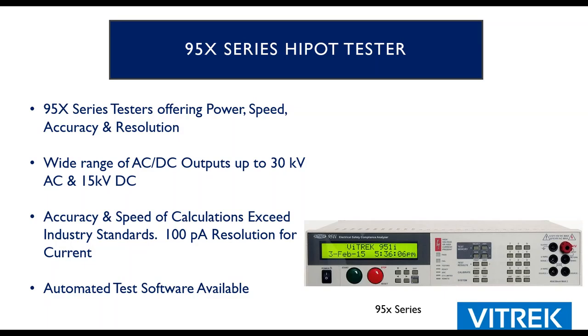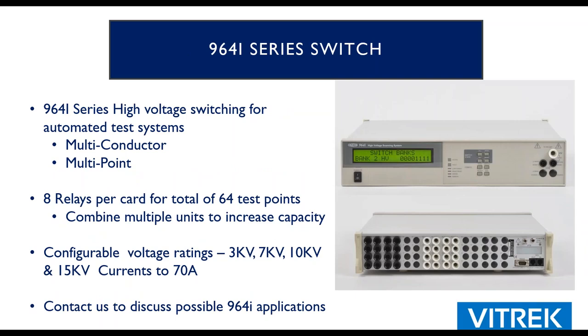The leakage current accuracy is in the hundreds of pico. The resolution is 100 picoamps, and we're good for total accuracy measurement of a nanoamp and a half or 2, which is really kind of unprecedented for most Hipot testers. This accuracy also allows us to do IR testing to about a teraohm in this product. So this is one of my personal favorites.